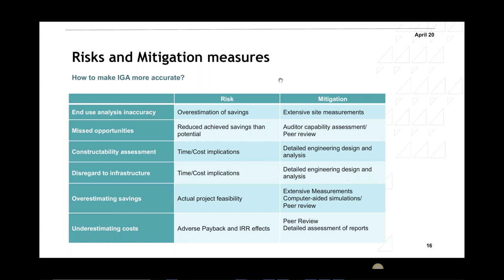Underestimating costs as well. I've seen it in a lot of audits. People assume that the costs are low because they don't do proper condition assessments. So you go to a site and say, okay, I'm going to put VFDs on your primary pumps, and it's a primary-only system, an old system, and this will save you a lot of energy. But it's a three-way valve system. You should probably be changing the valves as well, but that was not being considered during the energy audit. Then when they come to site, they find out, oh, we need to change the valves now. And the payback period jumped from 2 years to 5 years, which is not as per the client's requirements. The client maybe asked for 3 years payback maximum. So these things are very important. Proper condition assessment should happen on site.